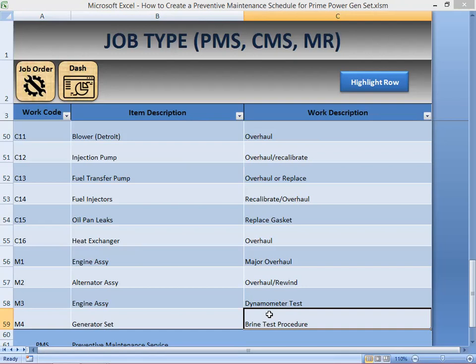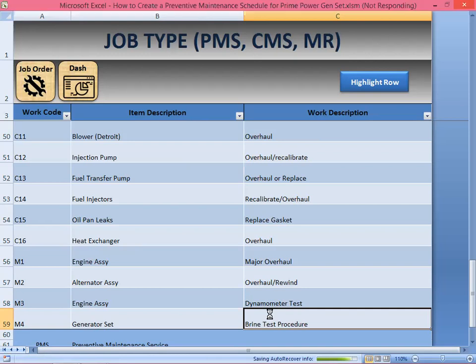What is the brine test procedure? This is some kind of tank filled with water and salt - that's why it's called brine. This is for the load testing of the generator. There are three phases in the generator - the bus bar. You submerge the bus bar while the engine is running, the dynamometer is running, the generator is running, and then you test the load. For example, if the generator has 2,000 kVA capacity, you find out whether the engine will supply the required horsepower and torque for the generator to supply the power needed, which is 2,000 kilovolt amperes (kVA). So this is the purpose of the brine test procedure.